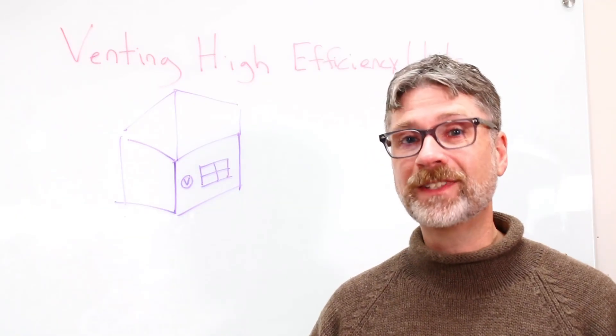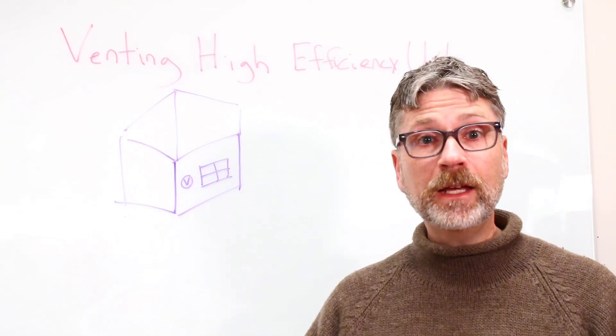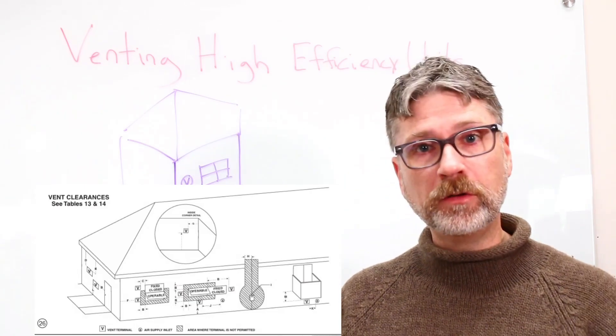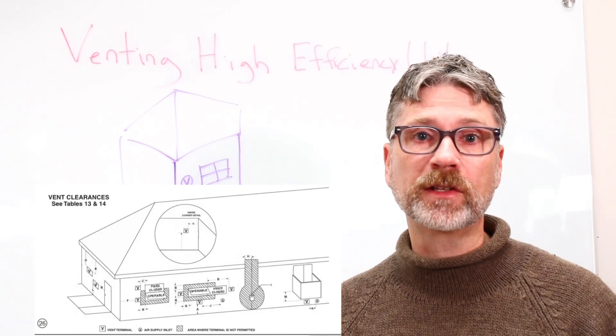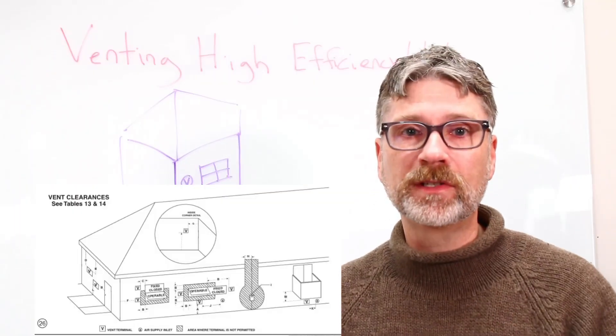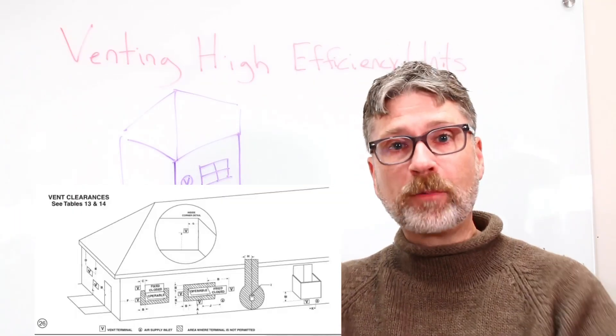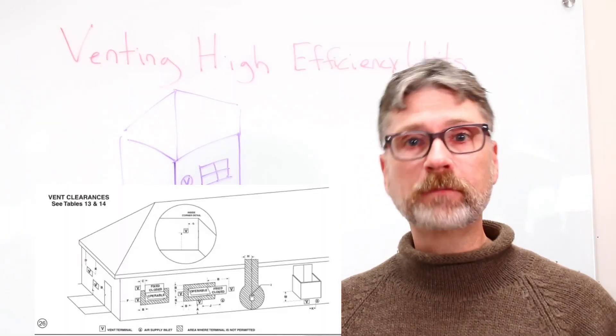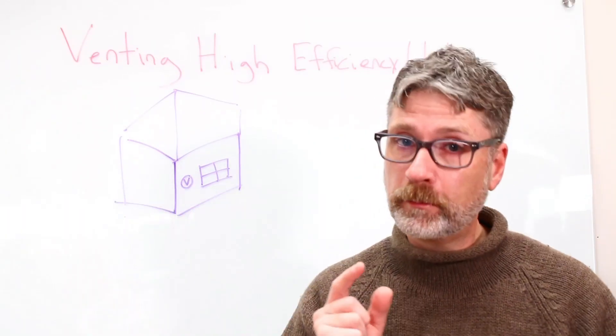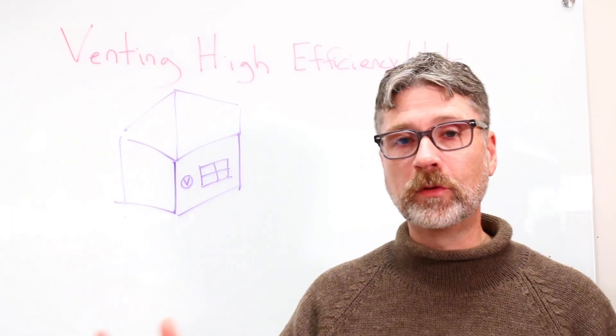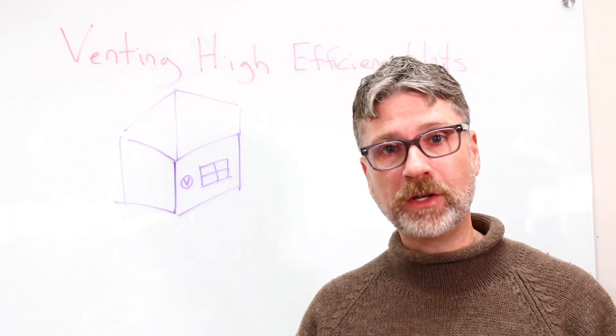Where you terminate your exhaust is a really big deal too. Again, the manufacturer will have a chart in the manual showing you the clearances to different things. And this is the minimum distance to things like, for example, an operable window. An inoperable window, a closed window that doesn't open, well the answer to that is zero. But the U.S. and Canada, for example, will have slightly different rules to different terminations.